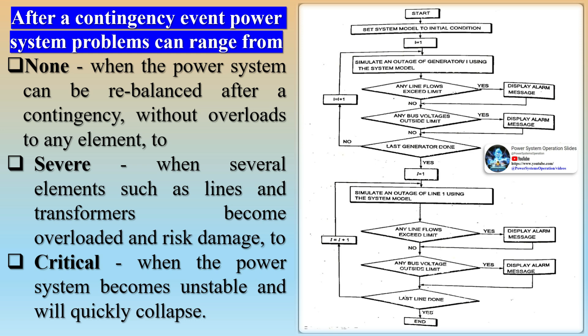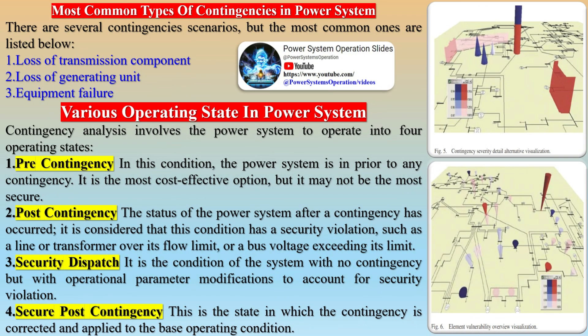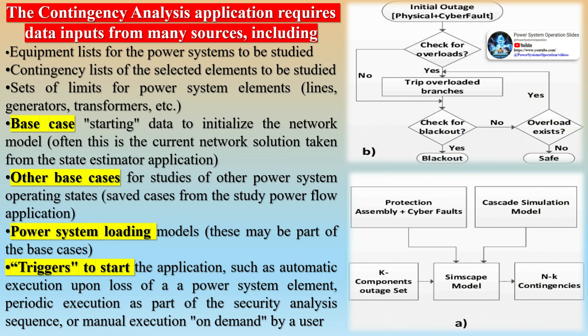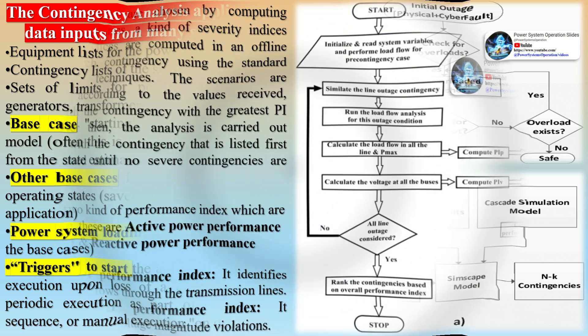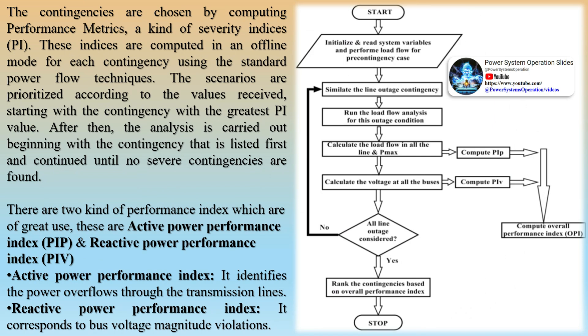An important part of security analysis revolves around the power system's ability to withstand the effect of contingencies. The system security assessment process is carried out by calculating system operating limits in the pre-contingency and post-contingency operating states at an operation control center or at the Energy Management System (EMS) of the utility company. Contingency analysis is time-consuming as it involves complete AC load flow calculations following every possible outage event. To mitigate this, an automatic contingency screening approach is adopted, which identifies and ranks only those outages that cause limit violations on power flow or voltages. The contingencies are screened according to a severity index or performance index, where a higher value denotes a higher degree of severity.